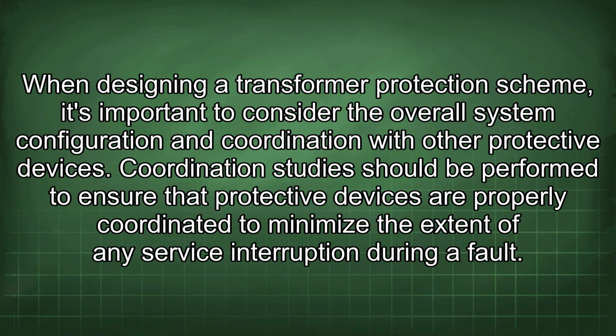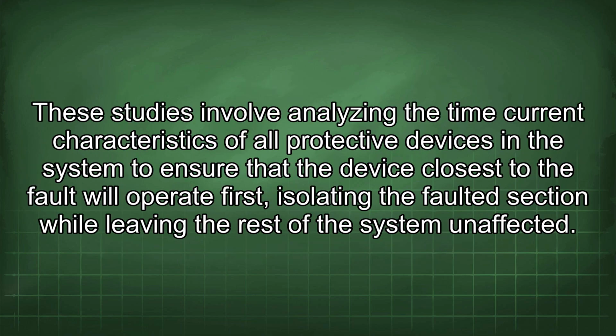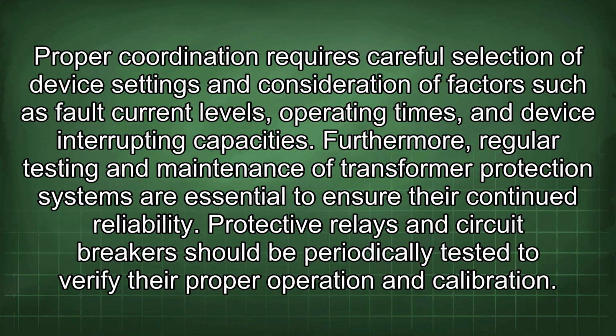When designing a transformer protection scheme, it's important to consider the overall system configuration and coordination with other protective devices. Coordination studies should be performed to ensure that protective devices are properly coordinated to minimize the extent of any service interruption during a fault. These studies involve analyzing the time current characteristics of all protective devices in the system to ensure that the device closest to the fault will operate first, isolating the faulted section while leaving the rest of the system unaffected. Proper coordination requires careful selection of device settings and consideration of factors such as fault current levels, operating times, and device interrupting capacities.